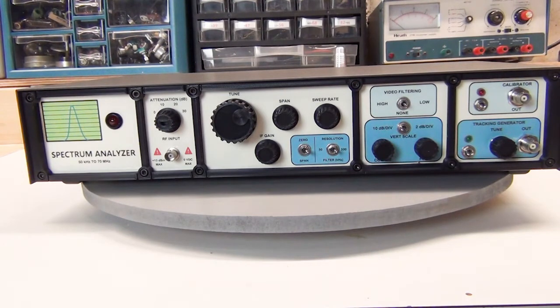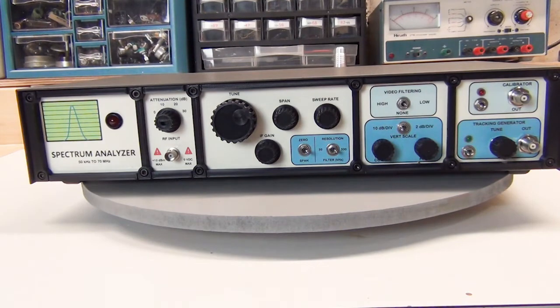And then finally, over on the right are the two additional features that the spectrum analyzer design has. There's the calibrator that you can turn on that has a reference signal every 10 megahertz. And then here's the tracking generator. And there is a fine-tuned control that you can adjust to set the tracking frequency a little more accurately.